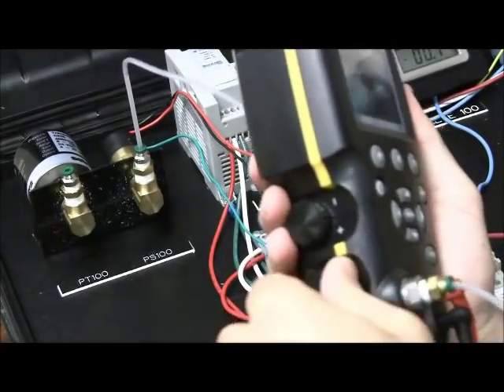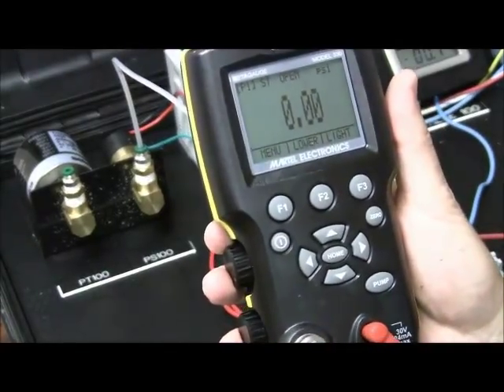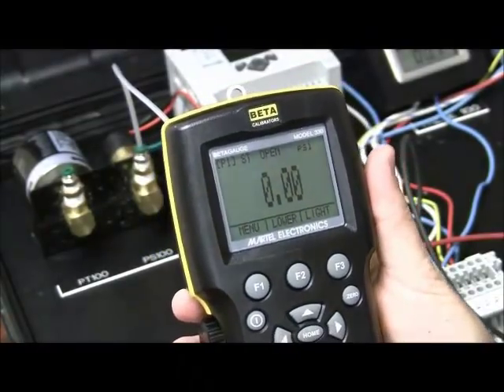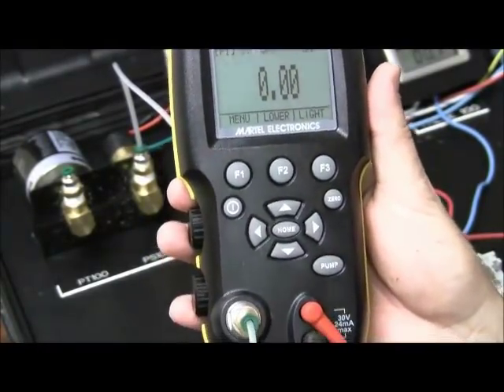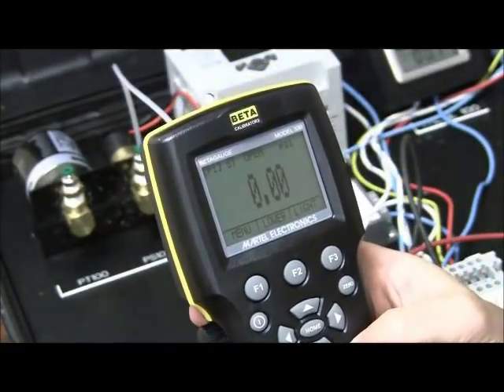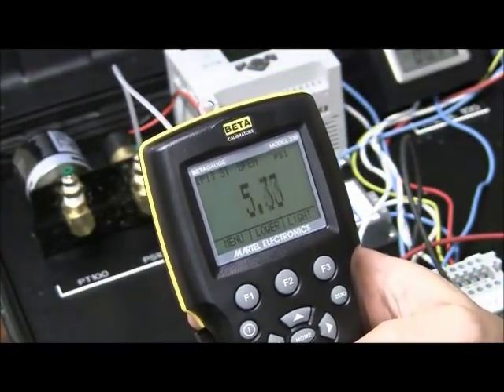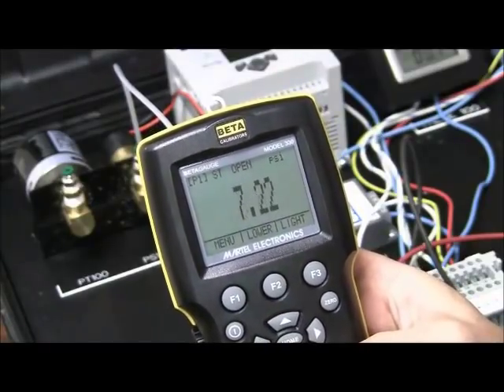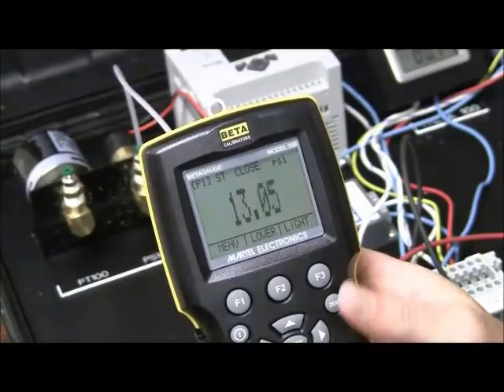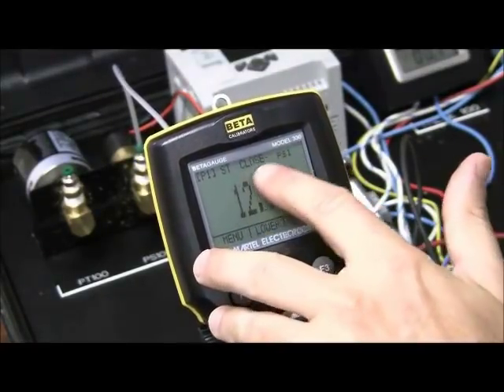I'm going to close my vent here on my 330. I'm going to pump up. Now I have it set to about 10 PSI, which is pretty low for this pump, because I have a 150 PSI version here. So I'm going to pump up really slow here. Still open. Alright, so you've seen it change state here, close.